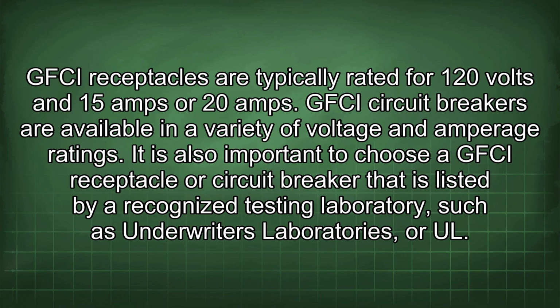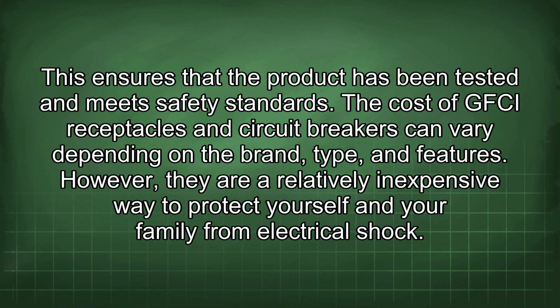GFCI receptacles are typically rated for 120 volts and 15 amps or 20 amps. GFCI circuit breakers are available in a variety of voltage and amperage ratings. It is also important to choose a GFCI receptacle or circuit breaker that is listed by a recognized testing laboratory, such as Underwriters Laboratories or UL. This ensures that the product has been tested and meets safety standards. The cost of GFCI receptacles and circuit breakers can vary depending on the brand, type, and features. However, they are a relatively inexpensive way to protect yourself and your family from electrical shock.